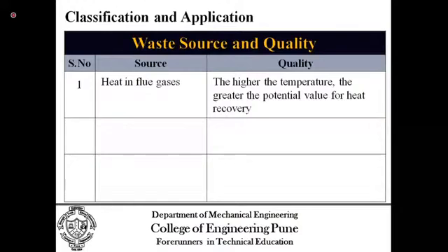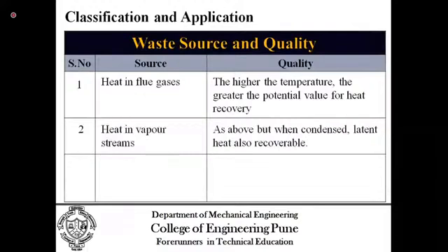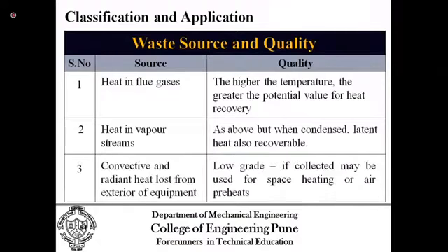Second is heat in vapor streams. Most of the vapors do contain some heat in the form of their latent heat. That latent heat can also be recovered. You must be knowing the flash steam recovery system. The condensate is converted into flash steam, and this flash steam is then recovered. So it is nothing but recovery of the heat in the vapor stream. And the surfaces from which the equipment is made can be at a higher temperature, and thus these surfaces will lose heat by convective and radiative heat transfer.